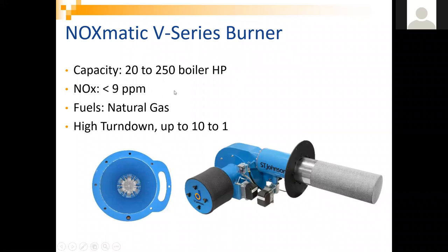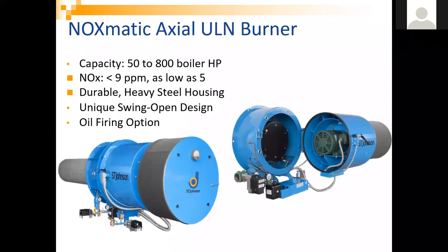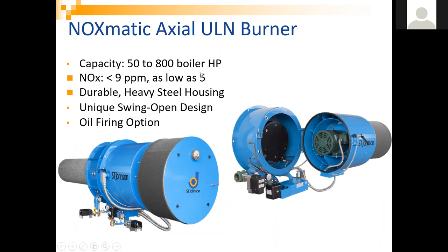The NOXmatic V-Series achieves sub-9 PPM, and we have done sub-7 PPM on this burner, with an 8-to-1 or 10-to-1 turn down — a very high turn down burner. Higher turn down means the boiler cycles less, turning on and off less, which reduces wear and tear on burners, motors, electrical components, starters, VFDs, and igniters. The NOXmatic axial ULN burner is hinged for ease of service — you can change out the element and motors directly through the hinged port. We can hit sub-5 PPM with this burner, which can also fire oil, going up to 800 horsepower and even up to 1,200 or 1,300 horsepower.